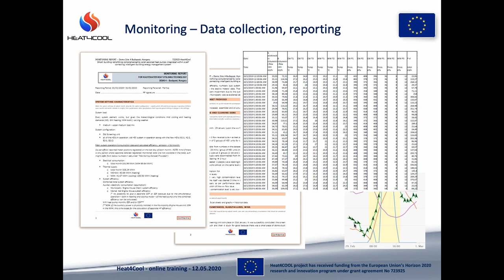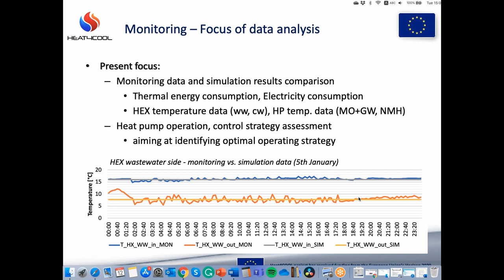Here you can see the data compared with what we had foreseen for wastewater flow and corresponding temperature. The steady gray line shows the foreseen value, close to 15 degrees Celsius. The orange and red lines show that after heating — meaning after we cool down the wastewater flow — the temperature is nearly 10 degrees Celsius. So as foreseen, we achieve about a 5 degree Celsius change, which allows us to produce heat from the wastewater flow.